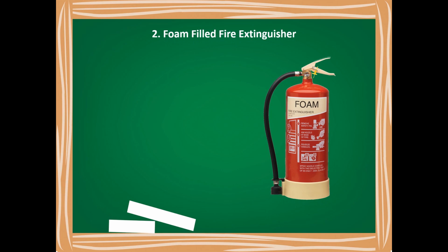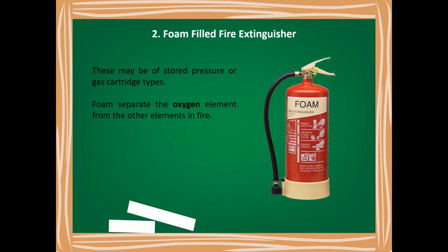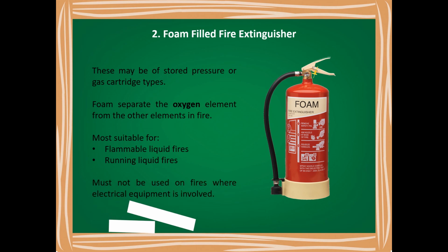Foam-filled fire extinguisher. These may be of stored pressure or gas cartridge types. Foam separates the oxygen element from the other elements in fire. More suitable for flammable liquid fires, running liquid fires. Must not be used on fires where electrical equipment is involved.